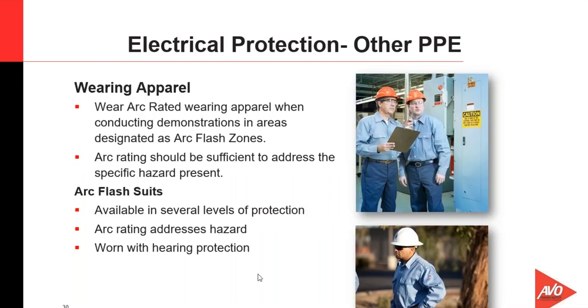Arc protection kind of comes in two different categories. We have wearing apparel. We could call that daily wear, and in this case, we're showing arc-rated flame-resistant wearing apparel being used by the workers. This is wearing apparel. Wearing apparel and PPE are two different things.